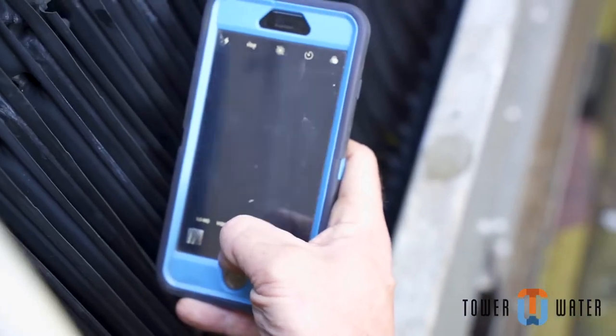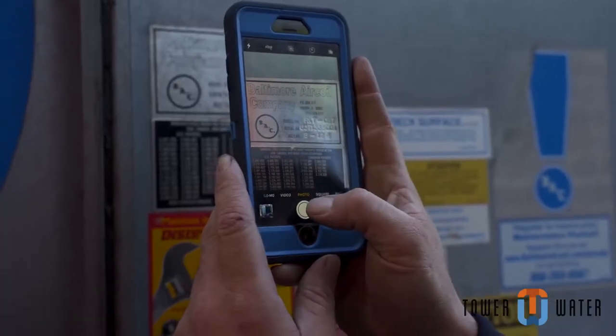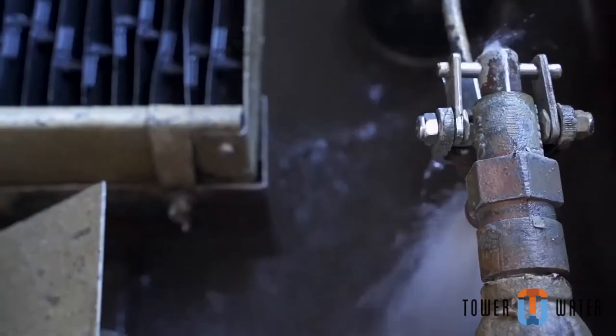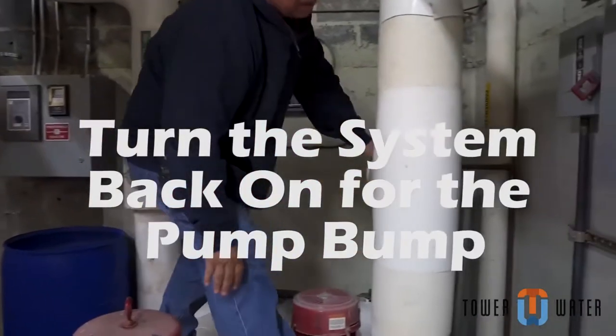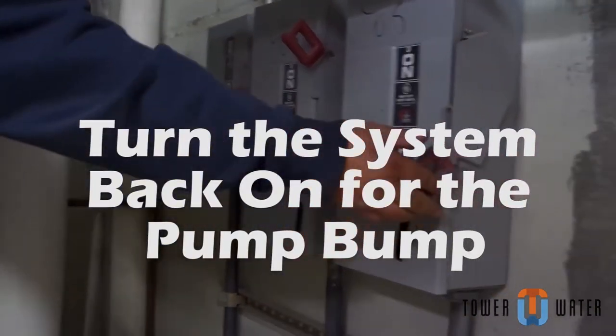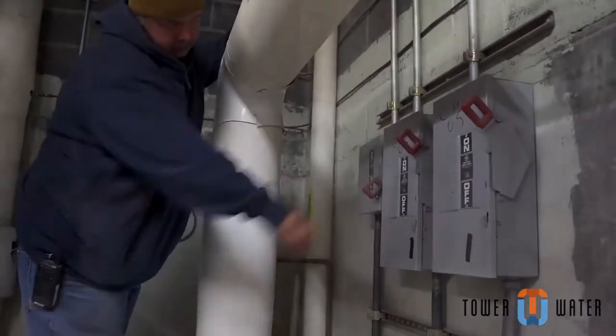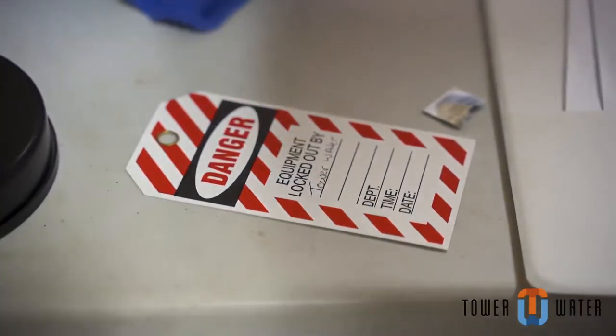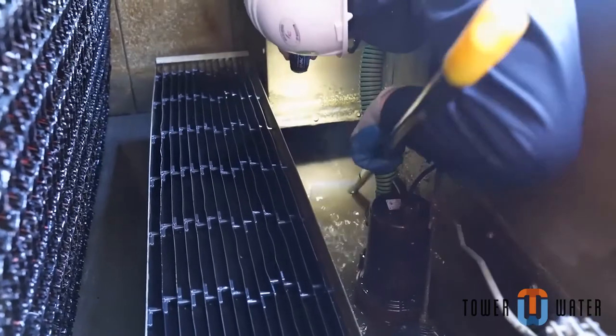Take photos of your successful cleaning at the same position as the before photos. Once the cleaning has been completed, begin filling the system by shutting the drain and opening the makeup. For towers where your fire hose cannot provide high volume water, substitute the pump bump procedure. This is done by removing locks and tags from tower recirculating pumps and having the customer turn them on for 5 seconds then off. Do this 2 to 3 times. Replace the locks and tags and quickly re-clean the basin of the tower only.